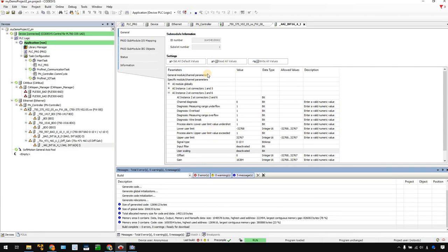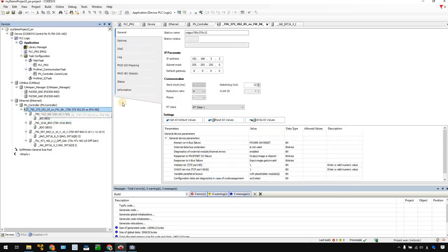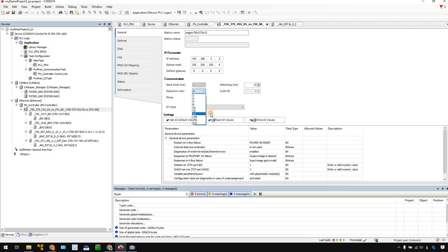Now it's done. But there are some parameters you may need to set. Go back to your coupler. The reduction ratio is 4, which means the cycle is very fast. Maybe this CPU cannot accept such a fast update time. You can change it to a little bit slower. Then download again.